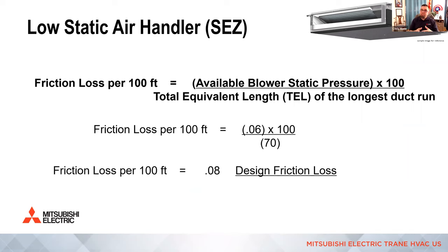We need to make sure design friction loss stays between 0.06 and 0.16. And if you remember, that was that chart on the friction rate worksheet that we sent out. It tells you if it's too low, then you need to increase blower speed, which is really hard to do with a low static air handler, or use a different system, a larger blower, or reduce your equivalent length value to get the friction loss back up. All right. If it's too high, then you need to decrease the blower speed, use a lower static.